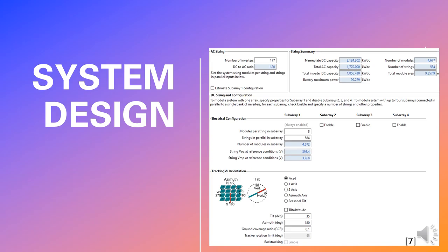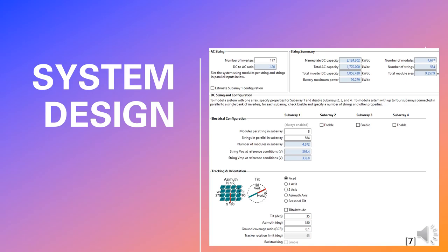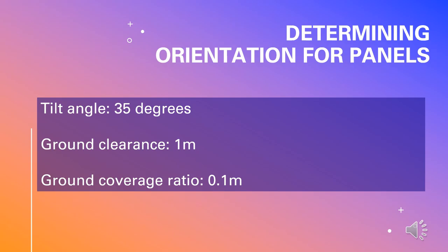We implemented the information we obtained for the inverter in the system design tab. We changed the number of inverters and module configurations for a standard DC to AC ratio of 1.2. Tracking and orientation was kept fixed. Using a parametric function in SAM, we determined the optimal variables for tilt angle, ground clearance, and ground coverage ratio. It was found that a tilt angle of 35 degrees, a ground clearance of 1 meter, and a ground coverage ratio of 0.1 maximize our annual energy from the panels.